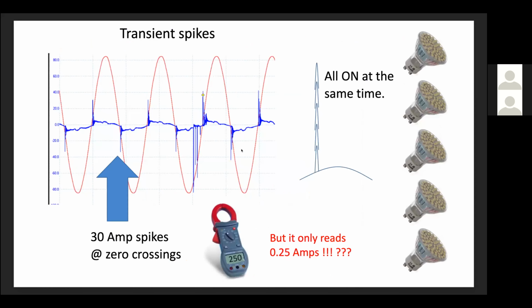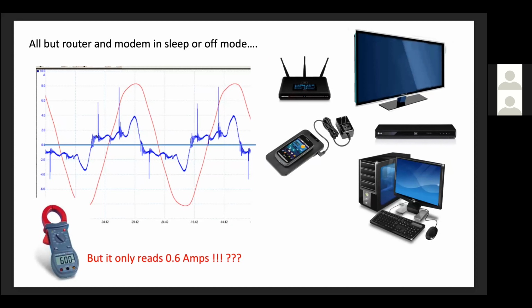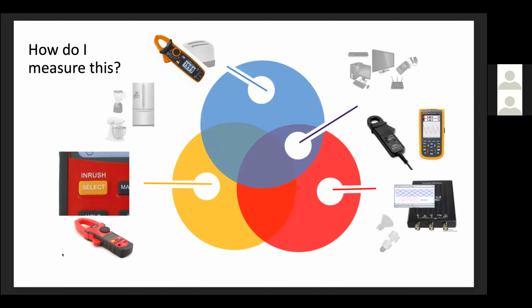Well, if you don't have an O-scope, how are you going to do that? Same thing for the transient spikes. A standard ammeter isn't going to show how high those transients are, and if they're added, what that cumulative effect might be if it exceeds the withstand characteristics of the PCS. Again, consumer electronics, same thing. Those transient spikes, when those switch mode power supplies fire, could be troublesome, and you cannot read them using a standard ammeter. So how would you measure those different types of loads when you're doing your load planning? Measuring to be sure and planning that backup loads panel is going to pay dividends. I have to stress this because this is the number one cause for service calls, truck rolls, after a battery system has been installed. So this is very important.